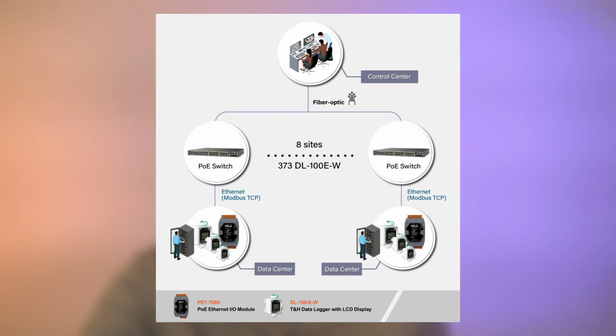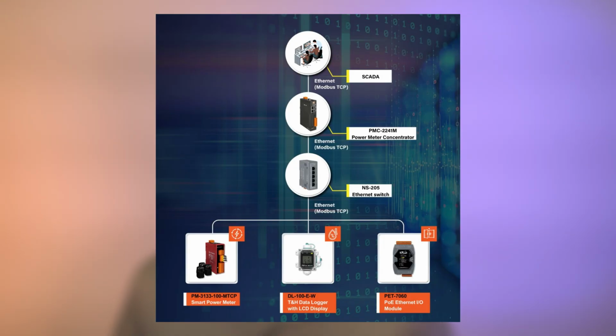For energy monitoring, install PM3133 meters at key distribution panels, PDUs, or high-load circuits and connect them to a PMC2241M concentrator. Use the concentrator's built-in logic to define alarms for abnormal voltage, current, or power factor. Forward those alerts to your existing alarm system or email notifications to your maintenance team.